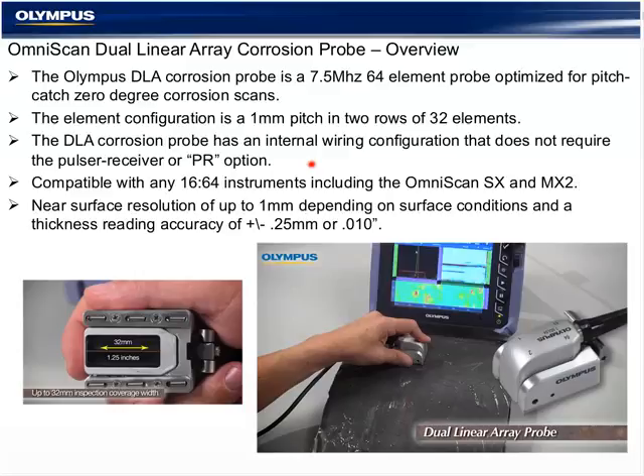The probe is a 7.5 megahertz 64-element probe optimized for pitch-catch 0-degree corrosion scans. So that means it has 32 elements on one side of the probe and 32 elements on the other side of the probe for a pitch-catch typical of 0-degree corrosion transducers used in both phased array and UT inspection. The element configuration is a 1 millimeter pitch in 2 rows of 32.